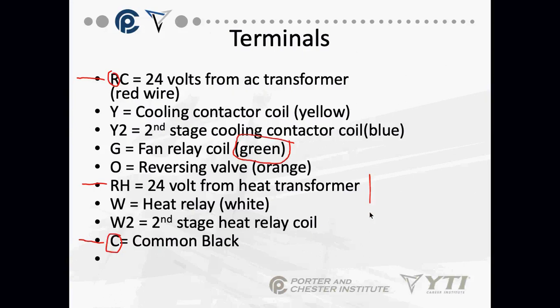Okay, because when we have our transformer on our low voltage side, you have your transformer coil. My R is on one side, and my C stands for common, and it is on the other side. You never want to take R to C without there being a load together in the middle. Any questions on that?